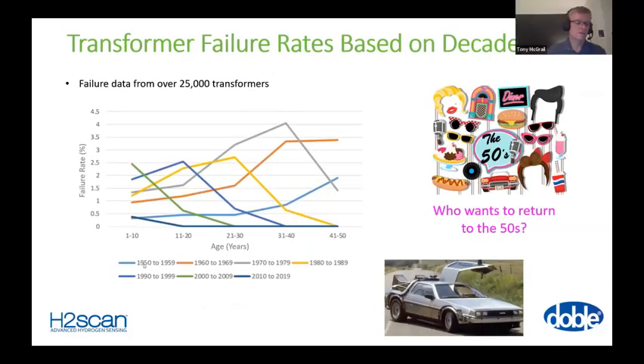So this is something I worked on with a colleague at Doble Engineering, Dr. Ronald Hernandez. He's done a lot of work on a huge database of transformers and failures that we've looked at over the years. What he did was look at individual companies, individual failure rates, how they changed year by year, decade by decade. So what I did was try to do a summary and say, for all the transformers that were built in our database from 1950 to 1959, what proportion of those failed in the first 10 years? What proportion failed in the next 10 years? What proportion failed in the 10 years after that?